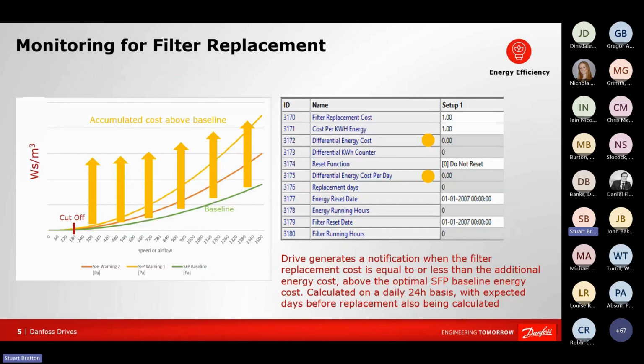Well, monitoring and just displaying a value is one thing, but what we can also do in the drive is what we call baseline that SFP value. So the drive can store internally the amount of watt seconds required to shift a particular amount of air. And what this allows the drive to detect, like I said, when it comes to condition-based monitoring, is that we're looking for changes in behavior of signals of the drive.